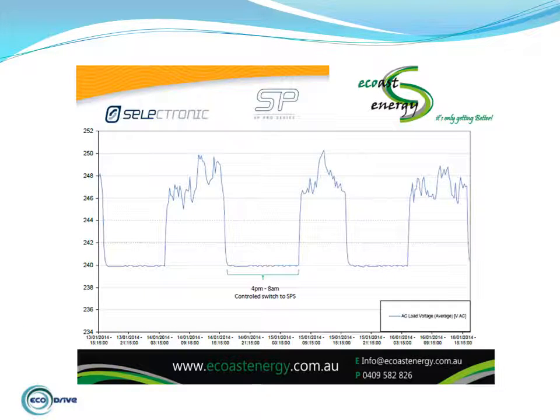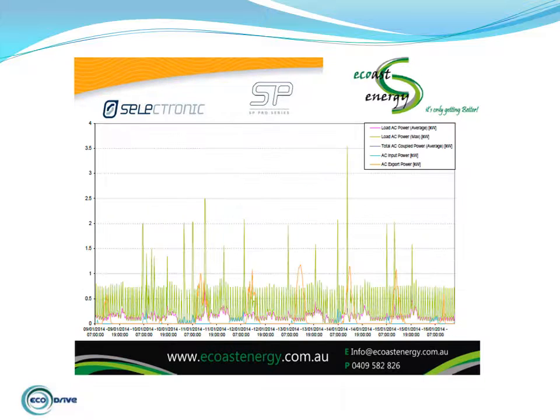The voltage waveform in the slide is taken from an installation where on a regular basis the inverter disconnects due to high voltage. Note the change in voltage when the array is in full sun. The effect is becoming more prevalent in many areas, particularly where there has been a vast uptake of PV grid systems. Consider the load versus PV input graph taken at the same location. Note the peak loading does not occur at the time of maximum PV output, meaning that a substantial quantity of energy is being transported to the grid.